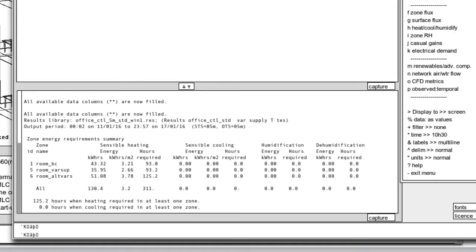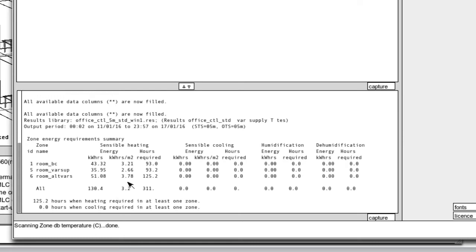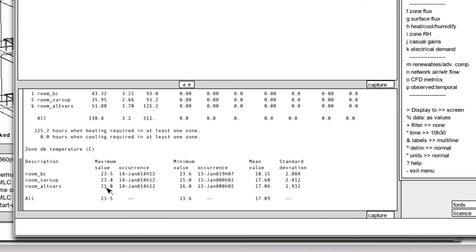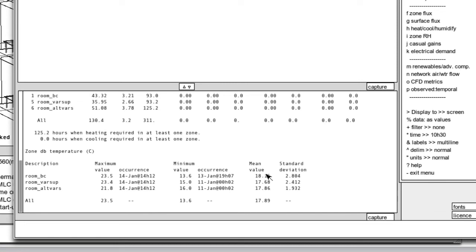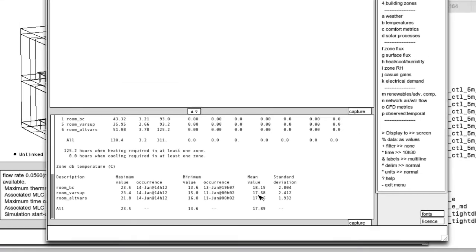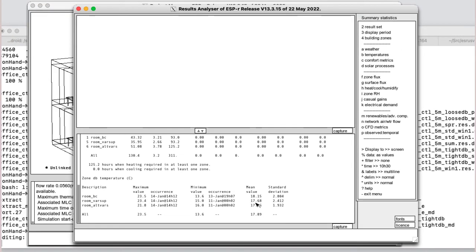And if I look at the summary statistics in terms of temperatures inside, slightly cooler than the altvars rooms. The minimum is a bit more. There's a slight difference between mean value in those different rooms. So now I could consider whether or not I need to increase the airflow rate, increase the supply temperature, or look at improving the fabric of the building. With very little input, I've been able to get some useful information.